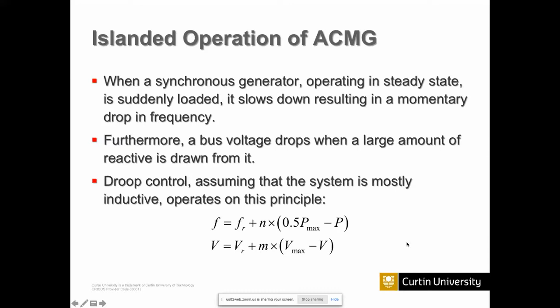So let's look at how it operates. Suppose these are two generators operating at 50 hertz, and suddenly your power requirement increases. As I mentioned, when the power requirement increases, the frequency actually drops. If this one supplies this much additional power, and this one supplies this much additional power, then the frequency of the entire system will remain constant. That's the basic principle of droop control. You cannot operate one generator at 50 hertz and another at 50.1 hertz in a system, your system will have large oscillations and damage. So that's not possible. That's the principle of droop control.